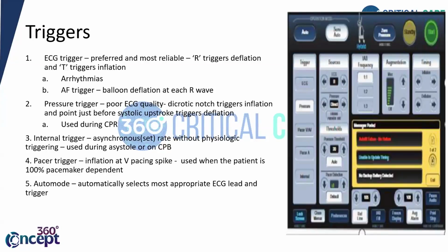Next, the pacemaker trigger, pacer trigger. So when your patient is on a pacemaker, it will use the pacing spike. The ventricular pacing spike is used for inflating the balloon. Okay. So next is auto mode. I told you, to make your job easy, this automatically selects the most appropriate ECG lead and that will be used as a trigger. So these are the common 5 triggers which are there, and this is the place on the interface where you'll set the trigger. Okay. Next, you can see the sources, ECG, and things like that.